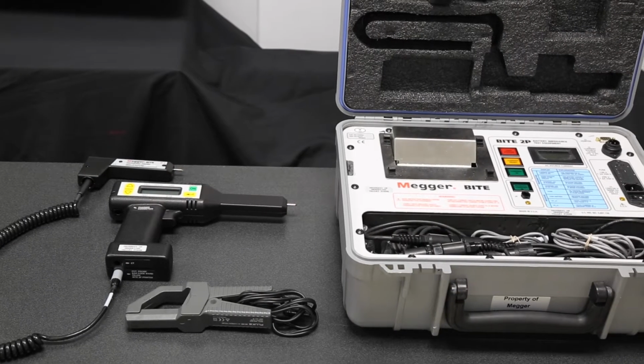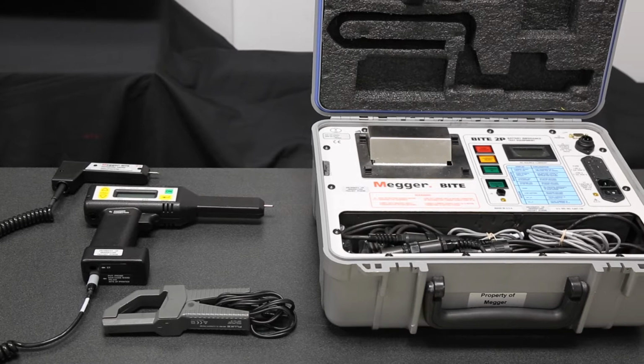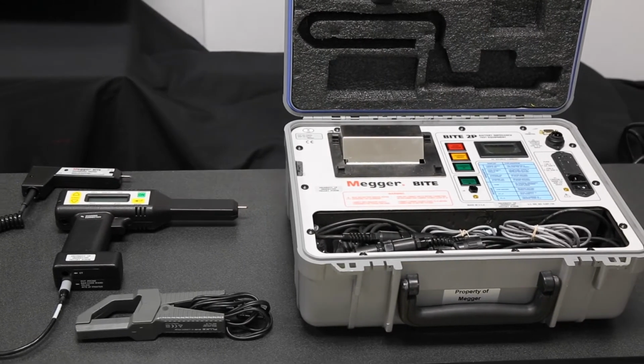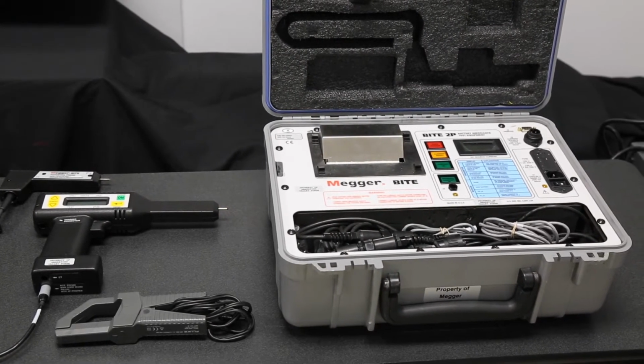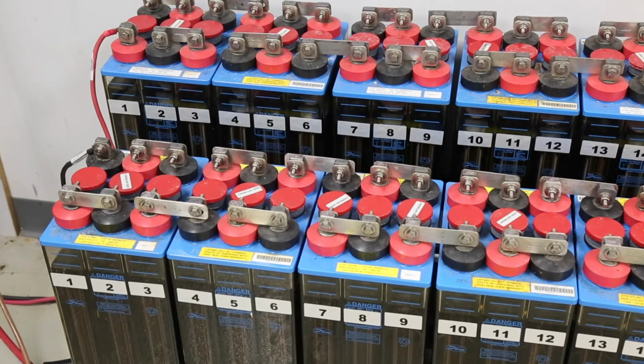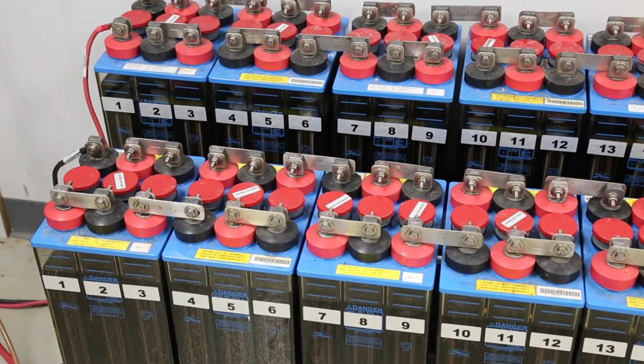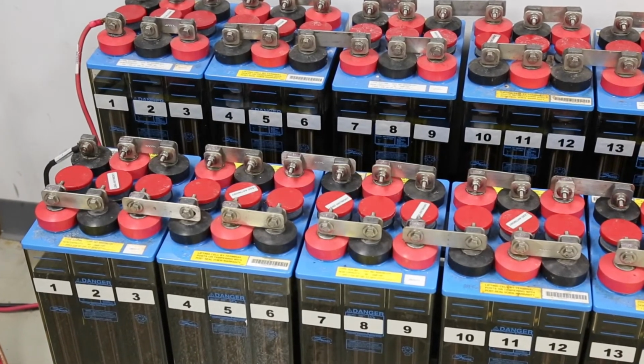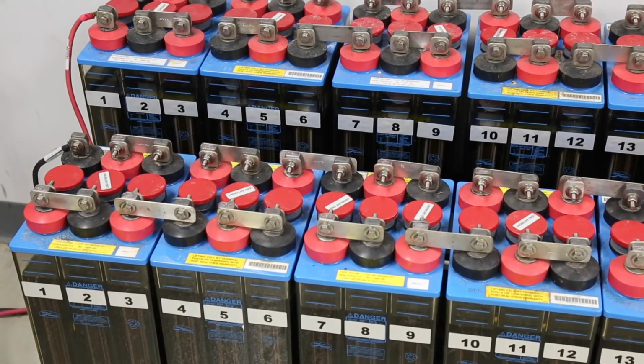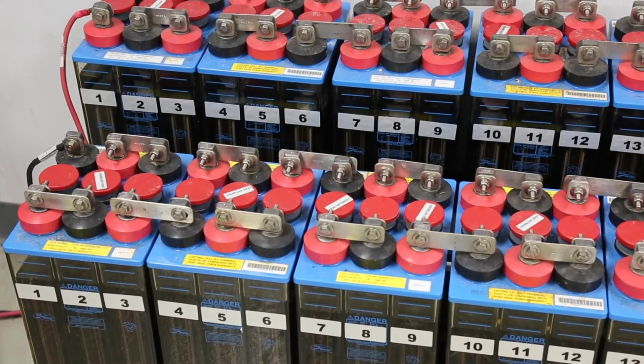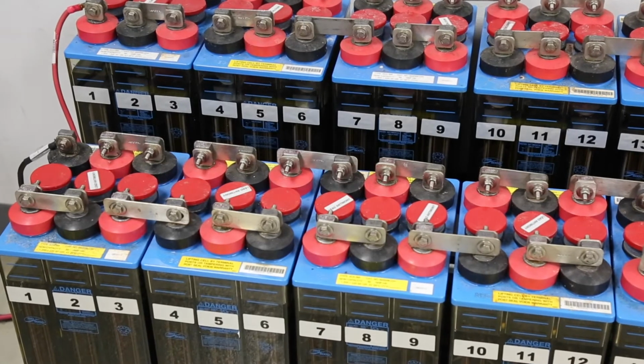BITE2 is a high current battery tester. It's designed to test large flooded batteries like those found in substations. As the capacity of a lead-acid battery increases, so does the active surface area of the plates within the battery. More surface area means more capacity and more current capability.